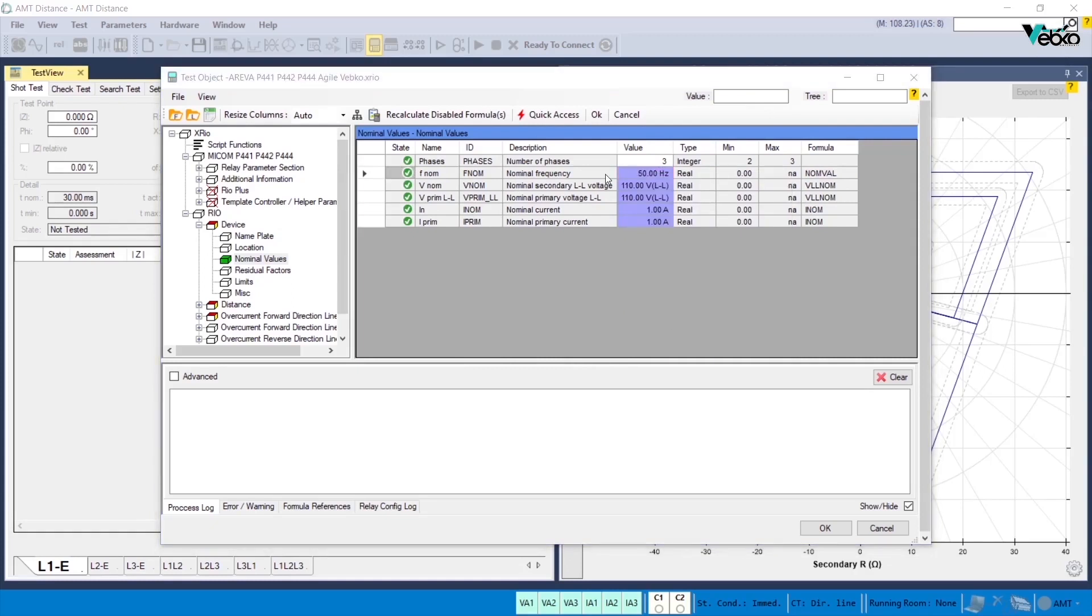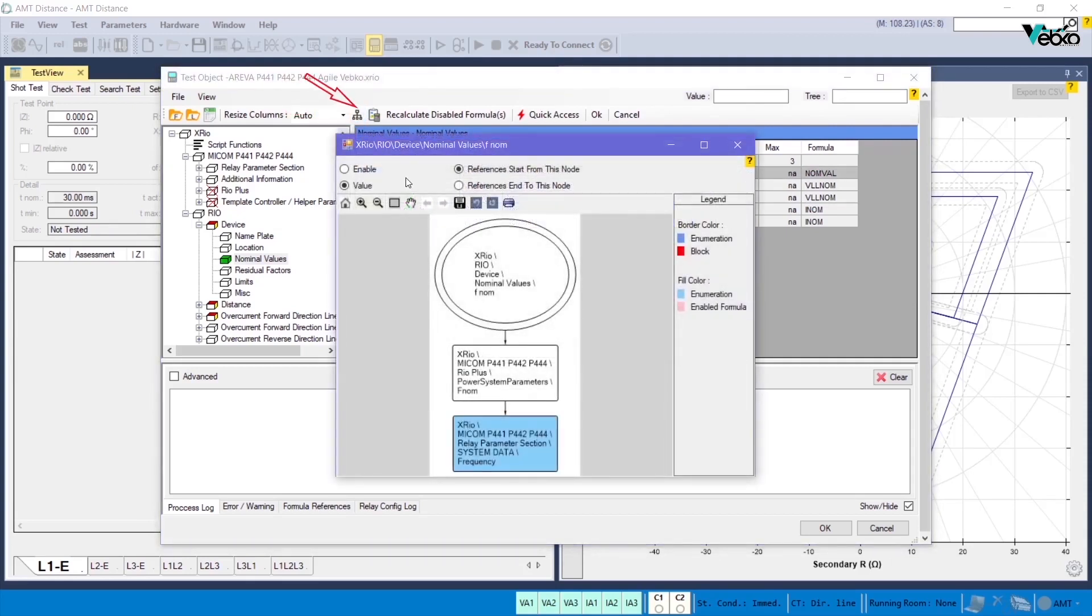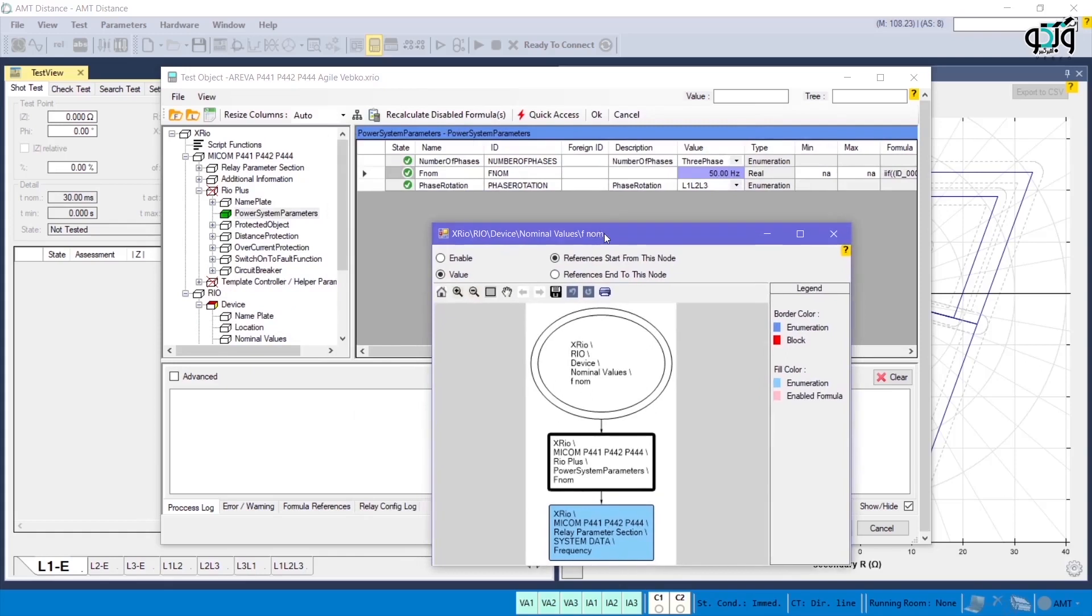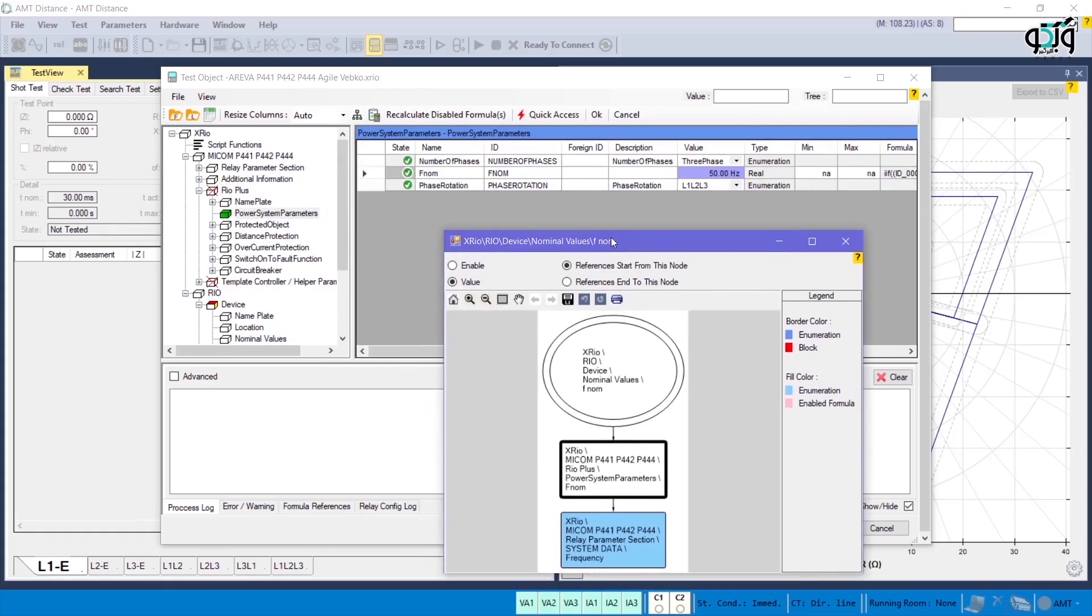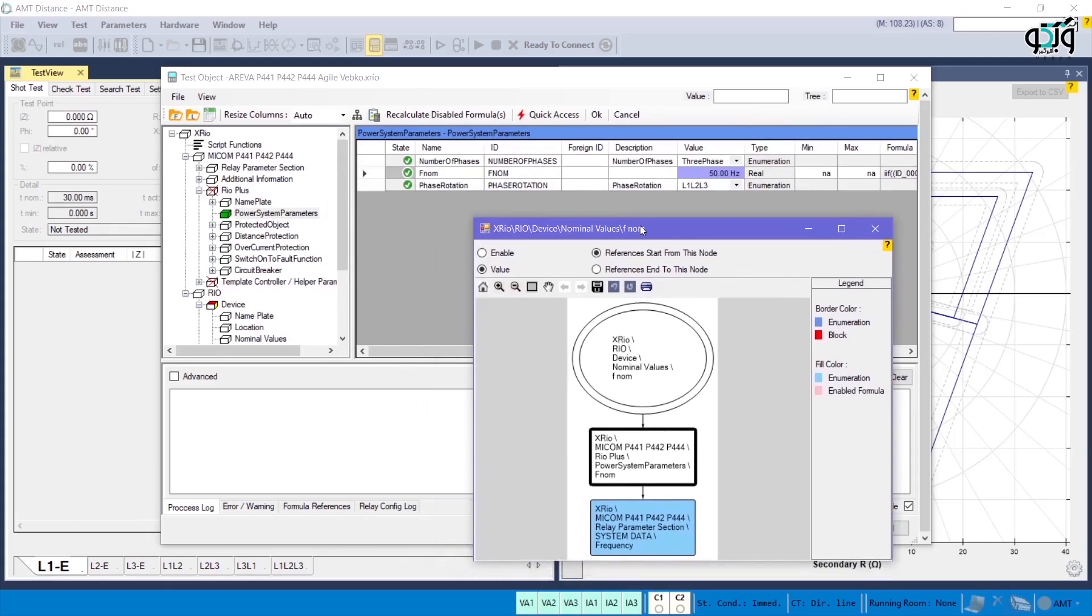To find out how the nominal frequency is defined, first you should select it, and then click on the reference map icon to view a map of the parameters to which the frequency is dependent on. By clicking on any of the boxes in this section, the parameter that affects the final value of the frequency is displayed, which in here the frequency is taken from FNOM.